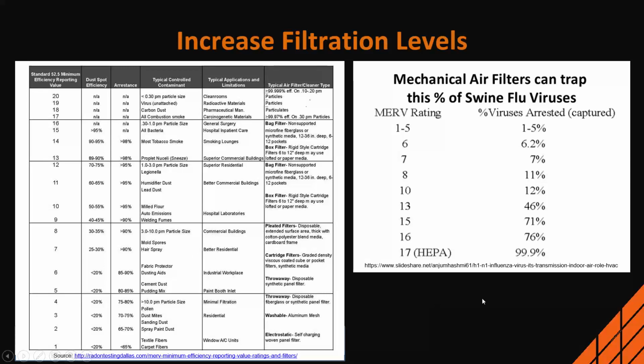And if you go to Home Depot or Lowe's, they are labeled. You really have to hunt a little bit because there's a lot more marketing information on there before you find the MERV rating. People will ask us about HEPA filters. Why not just put HEPA filters anywhere? Well, it goes back to the original statement a little bit about the resistance on those filters. So if you put in a HEPA filter, it's a very large filter. It's not practical in most applications.